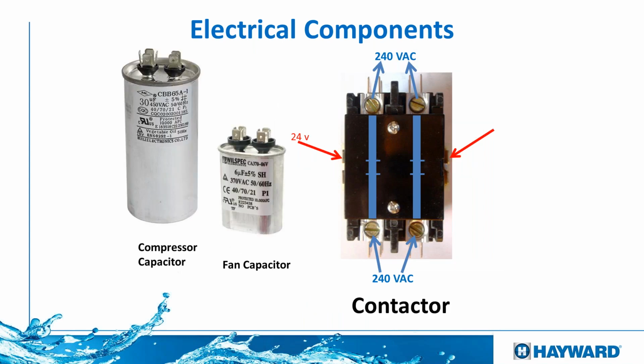If for some reason the unit does not start, but we do have 240, before you jump to conclusions, the first thing we can do is check the capacitor. The big one, as you can see here, is for the compressor. We need to disconnect that and make sure that we have enough microfarads in it. We just have to check that with a special meter that checks capacitors. Before you check that, make sure you short it out with a screwdriver or something so we can take the charge off of it, because they will stay charged for a while even if they are disconnected. And then you have this little capacitor, which is the one for the fan. Same thing, short it out and then check the capacitance, make sure you're good.